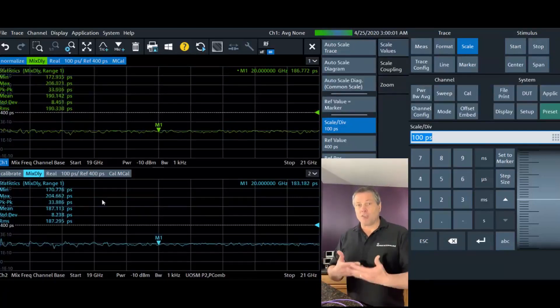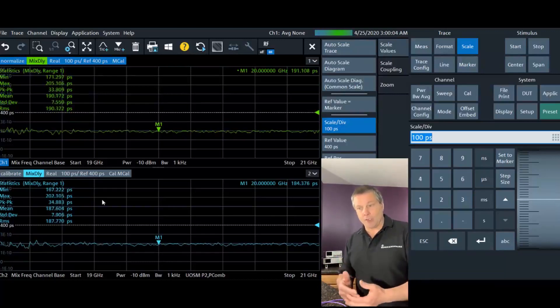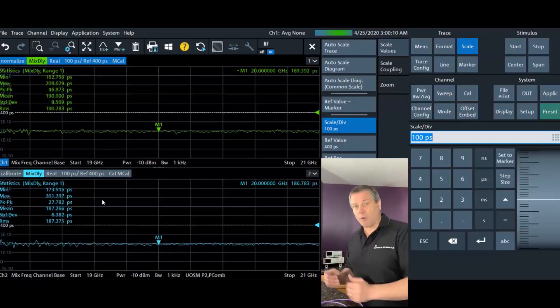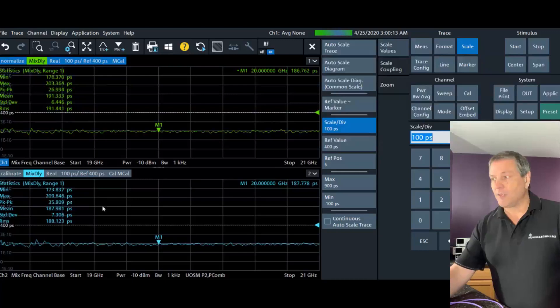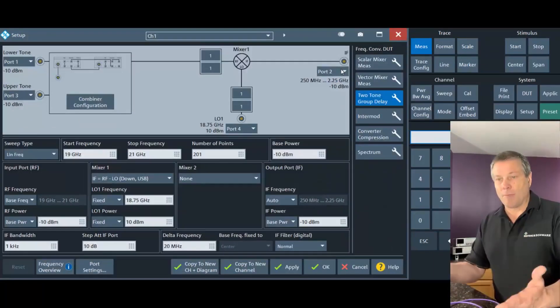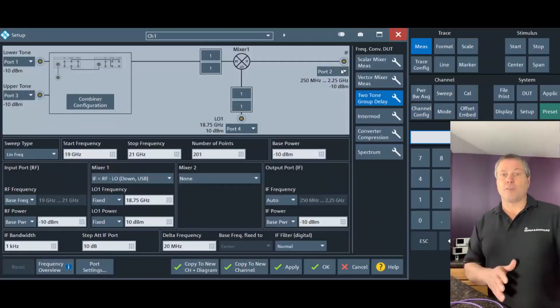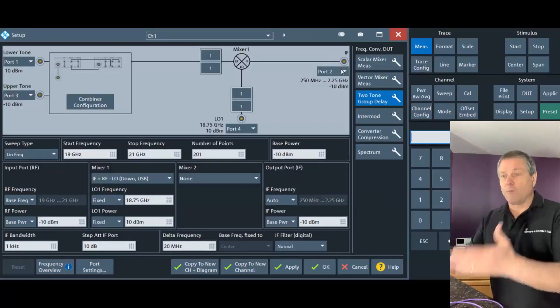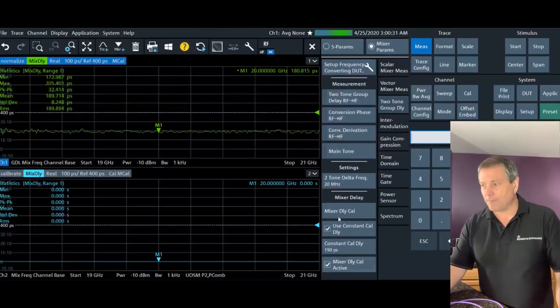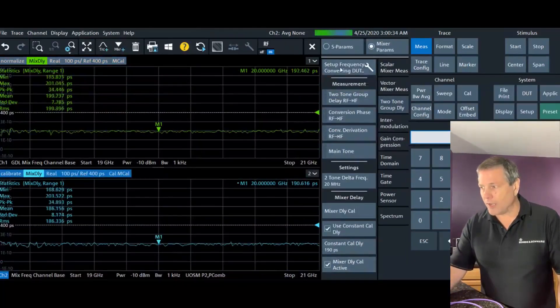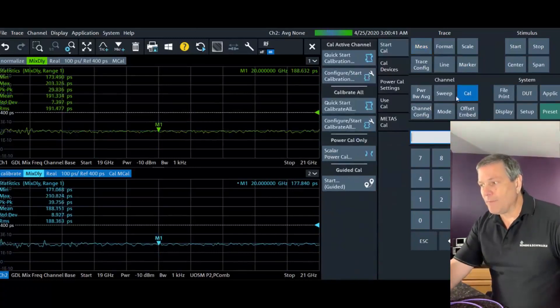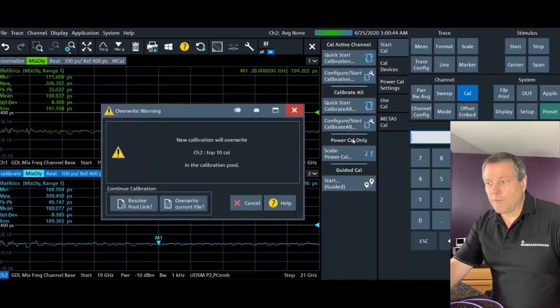In order to do that, let me show you what the calibration process looks like. Before we can calibrate a channel for two-tone group delay with S-parameter correction, we have to tell the instrument what the channel looks like. Normally you go to Measure, select Two-Tone Group Delay, and set up the measurement — filling in the dialog box as we've done in all previous videos. Once the dialog box is filled in, you're ready to calibrate the channel for S-parameter correction. I want to do this for channel two, then go to the Calibration key and configure this channel for calibration.